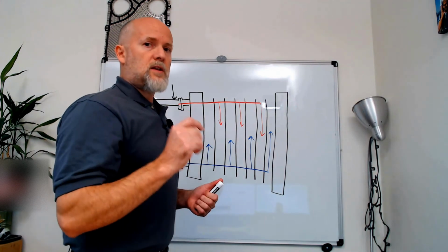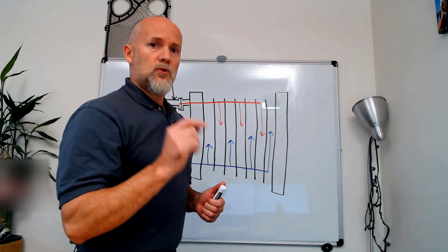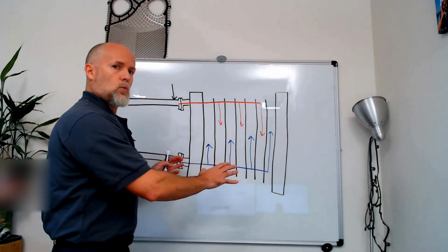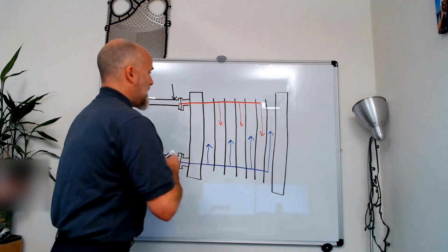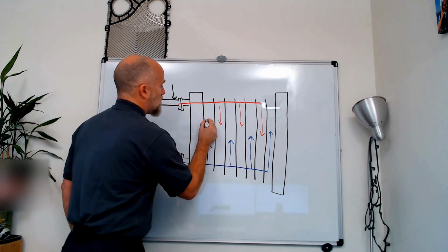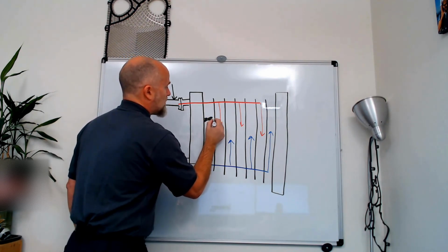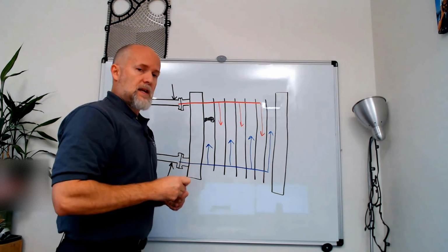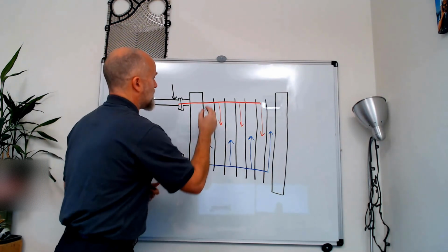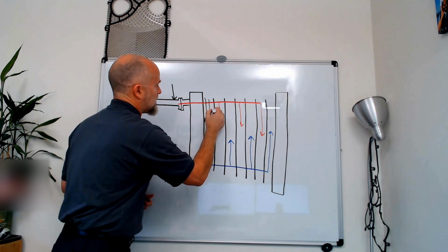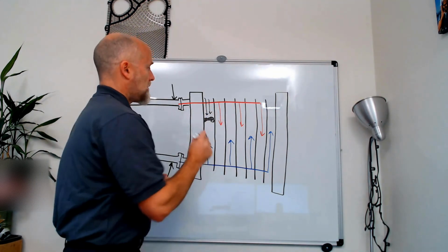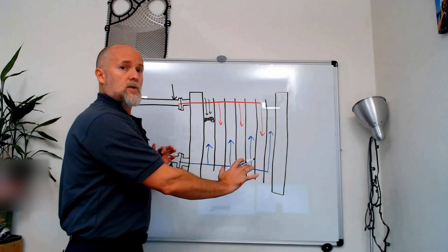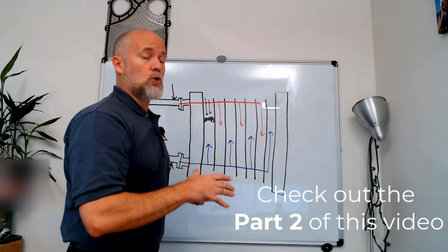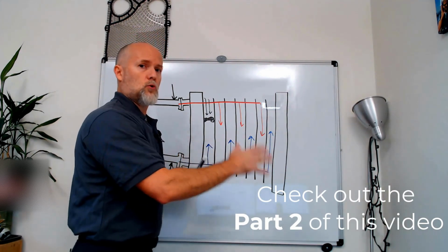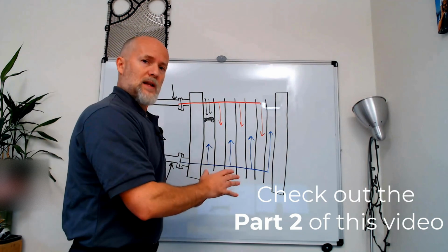Now, the key here is what we said, if it's not too dirty, because the CIP, in order to work, needs to go through the channels. And if the channels are so clogged that they are blocked, you understand that no chemical can go through this channel here, and so it doesn't clean anything. So it's important to time the CIP cycle in a way that the heat exchanger is dirty enough to need a CIP cycle, but not too dirty for the CIP not to work. And how do you do that? Let's have a look at that as well.